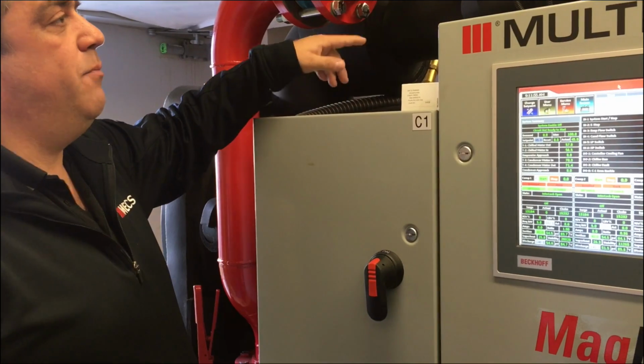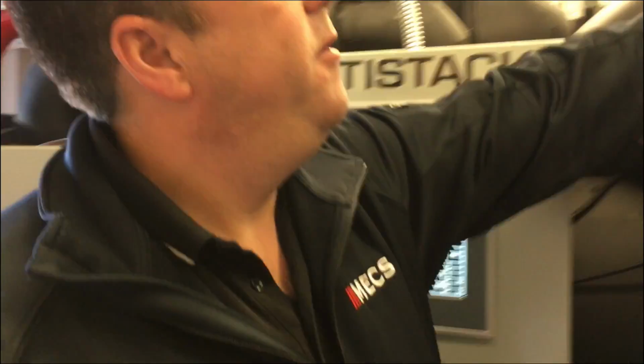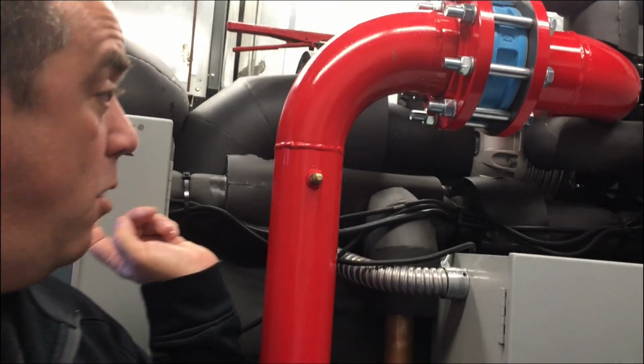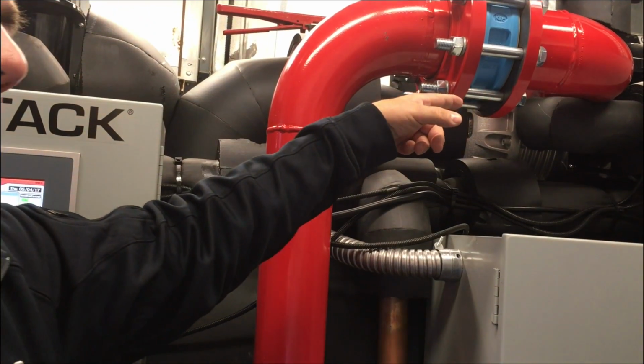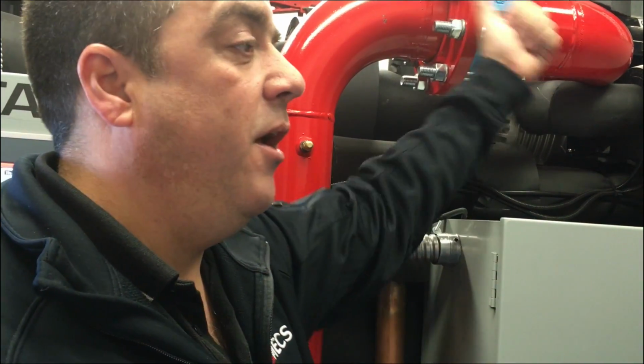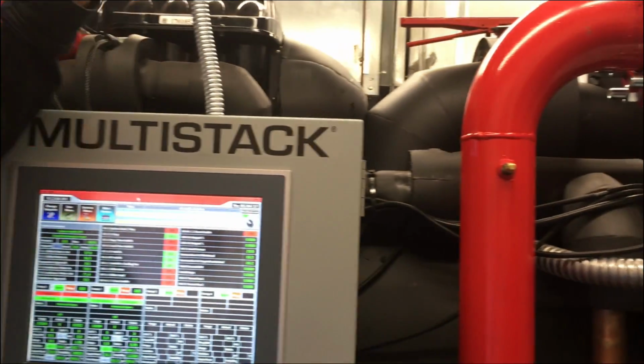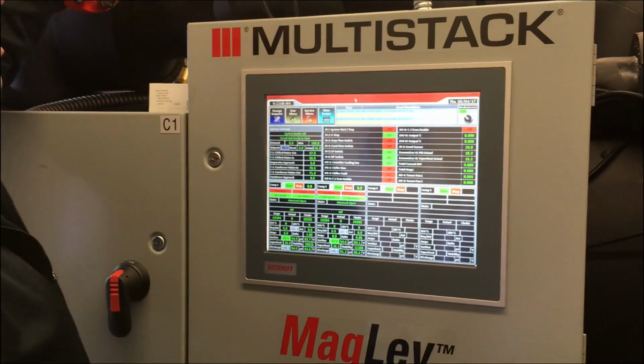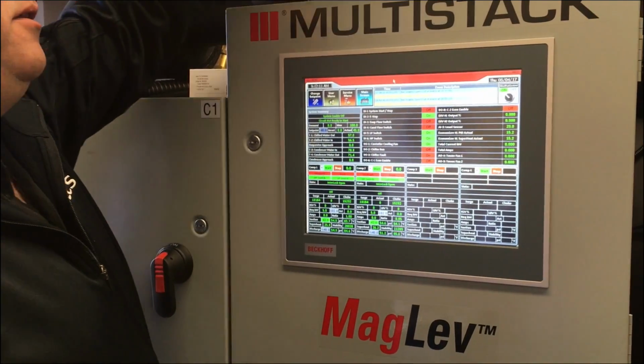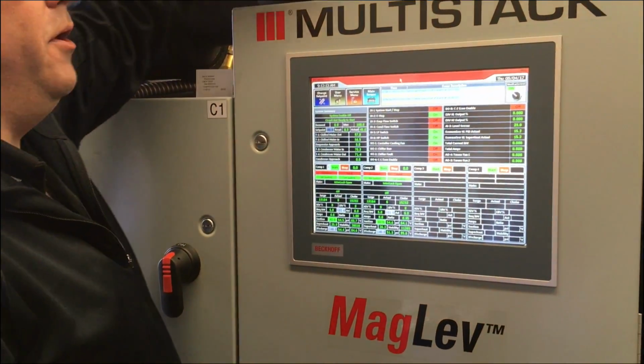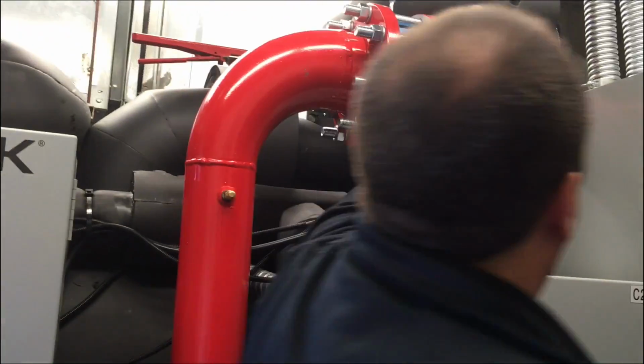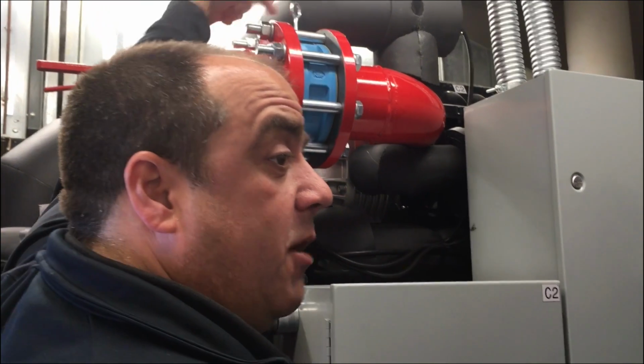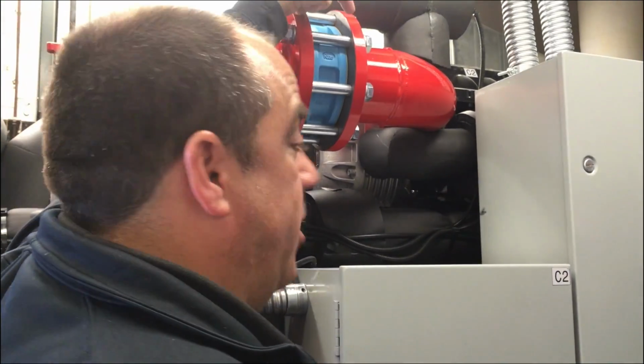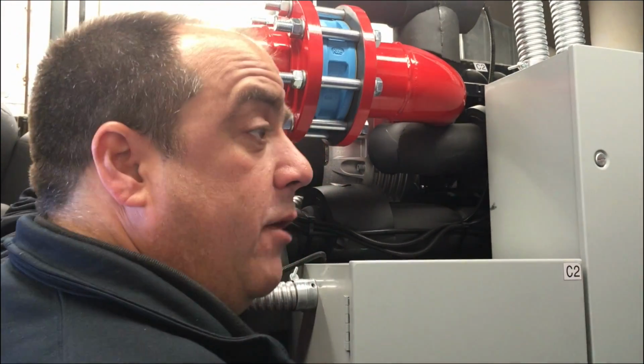So what happens is, if one compressor is running, the other compressor is relying on this check valve to stop refrigerant from going through it the other direction and backspinning. So this check valve will only let refrigerant flow that way. And that's why on startup, if this compressor is running, then that compressor wants to come in. They both do this even when no compressor is running. This valve right here opens, lets refrigerant flow in a little circle right here at the compressor, so it can get up to speed without having to fight the pressure of the rest of the system.